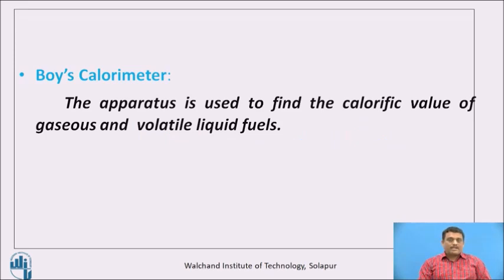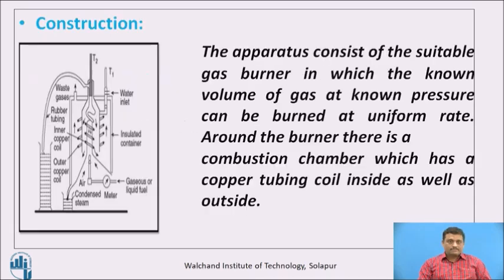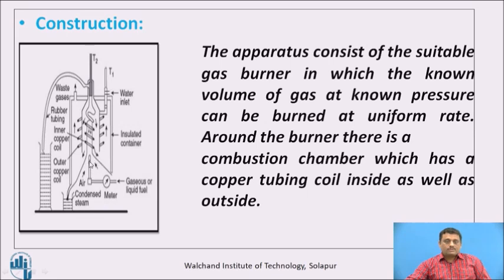The apparatus is used to find out the calorific value of gaseous as well as volatile type of liquid fuels. The apparatus consists of a suitable gas burner in which a known volume of gas at known pressure can be burned at a uniform rate. Around the burner there is a combustion chamber which has a copper tubing coil inside as well as outside. This is the combustion chamber, this is the burner, and this has a pressure regulator through which we can adjust the flow of the gas. When gas undergoes the combustion process, it evolves combustion products which accumulate inside the combustion chamber.